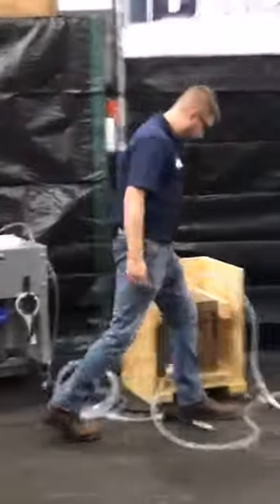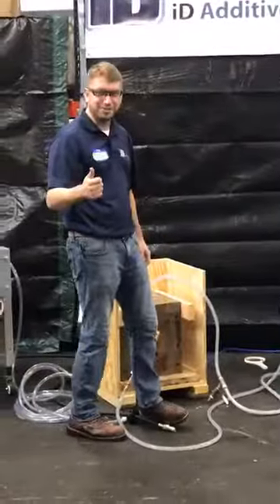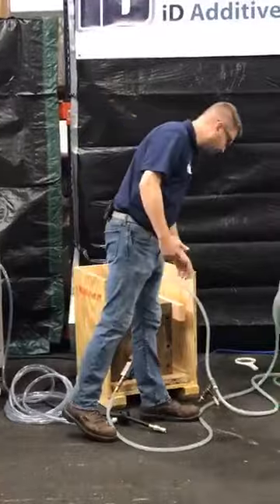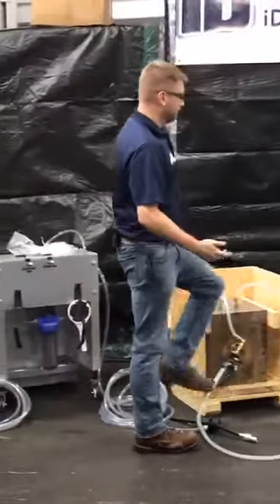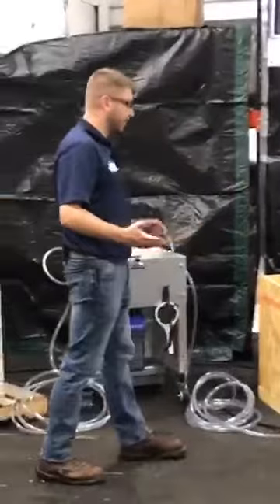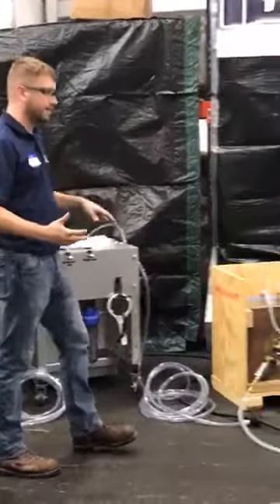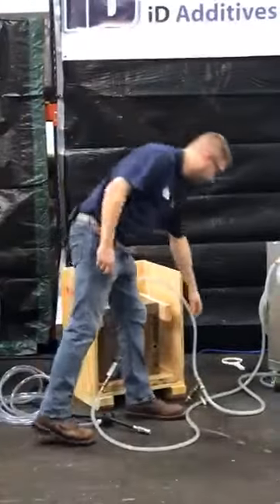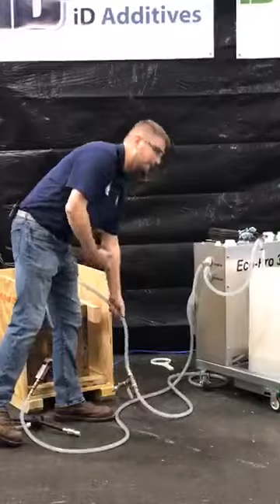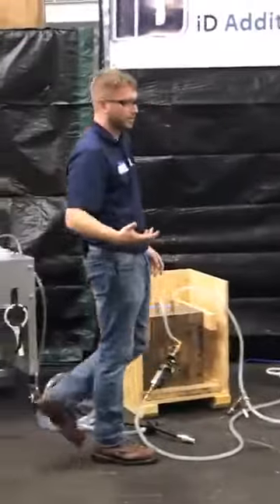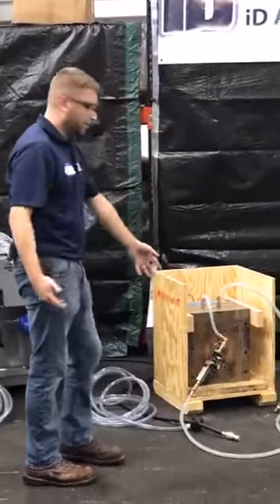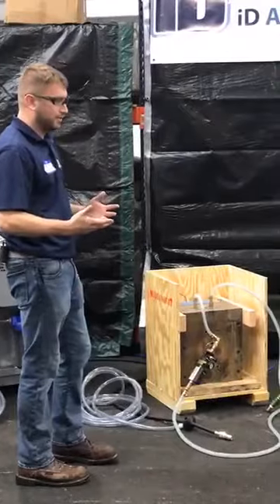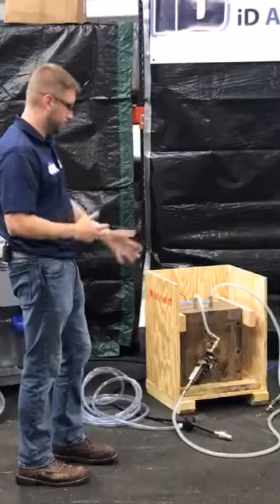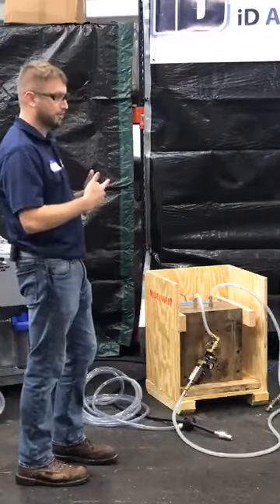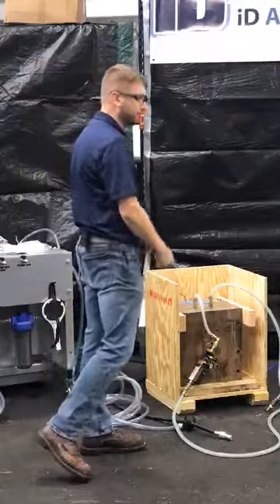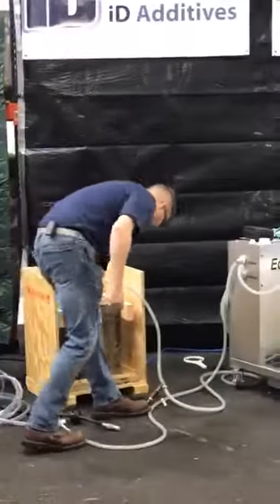Another feature I add—can you still hear me?—I recommend this a lot of times when you're in a shop and need to hook this up to clear out a blocked line. I added a release valve, because if you connect into a blocked line, you don't have a way to release that pressure. We sell the T-valve; you guys probably already have those components in your shop, and your shop guys can make that for you as well. But in case you run into a blocked line and need to back that pressure off, you can get rid of it.